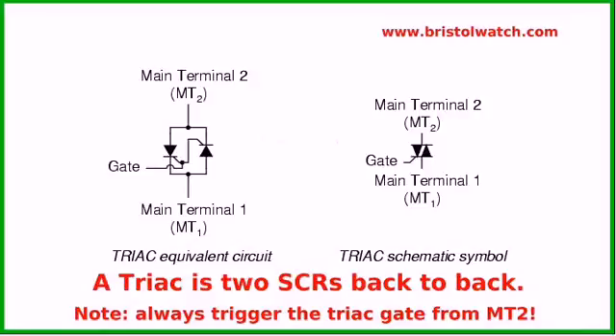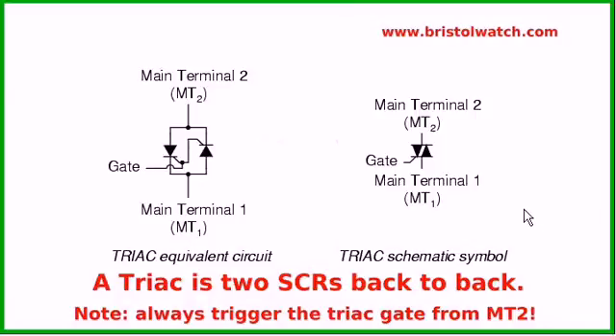Knowing that an SCR is a unidirectional device — only conducting current in one direction — we can take two SCRs connected back-to-back, cathode-to-anode and anode-to-cathode, and tie the gates together to have a solid-state switch that will conduct in both directions. What we end up with is a solid-state AC switch commonly known as a TRIAC. To summarize: a TRIAC is two SCRs back-to-back, and just like you have to trip an SCR from the anode, you have to trip the gate on a TRIAC from MT2.